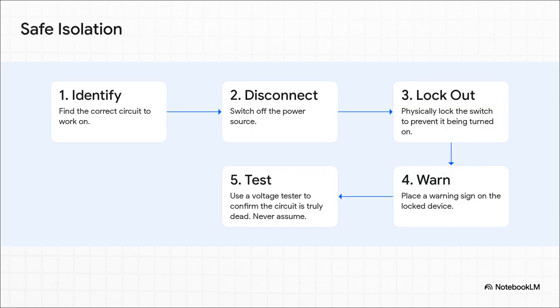All right, listen up, because this next part is absolutely critical. Before you do any work at all, you have to be 100% positive that the power is off. This 5-step process is called safe isolation, designed to completely eliminate any guesswork. Step 1, find the right circuit. 2, switch it off. 3, physically lock it so nobody can accidentally turn it back on. 4, put up a warning sign. And 5, probably the most important step of all, you test it. You use a proper voltage tester to prove that it's dead. You never ever assume, you always test.